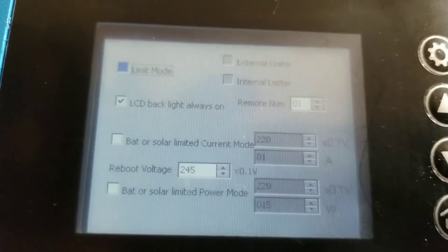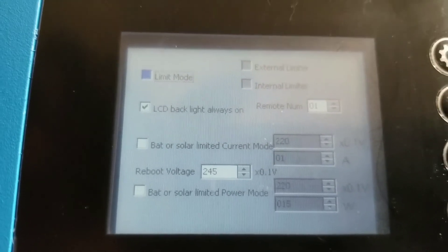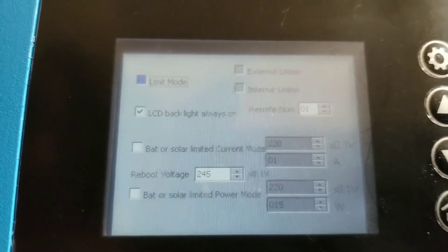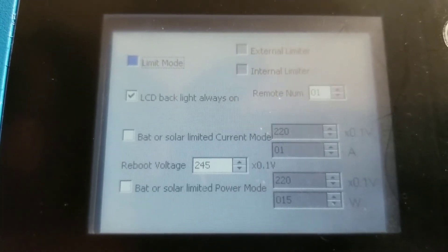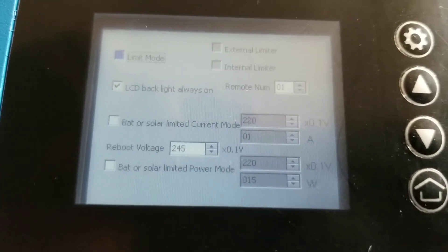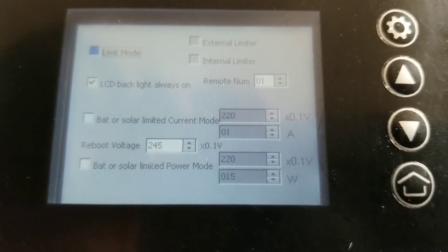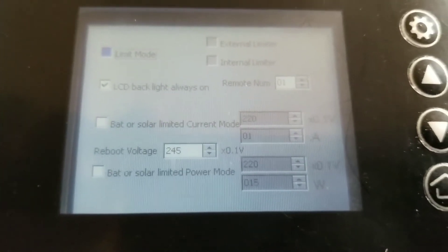This is another screen where you can do a lot of stuff. You can set this device to reboot at a voltage of 24.5 volts, set the backlight to always on, and choose from the options whether it's an internal or external limiter — we have an external limiter. There's also a power factor setting, and a battery limiter option where you can set a cut-off voltage so you don't drain or ruin your batteries.